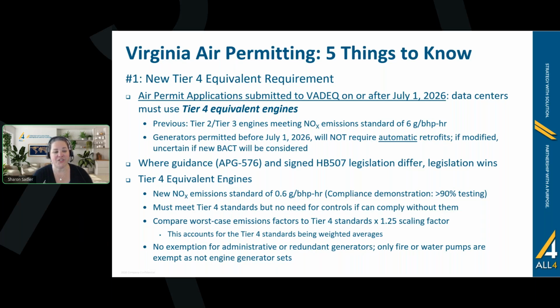To help account for the fact that Tier 4 standards are a weighted average, in your permit application, if you're trying to assert that you can comply with the Tier 4 standards, you're actually going to compare your engine data to the Tier 4 standard with a 1.25 scaling factor.